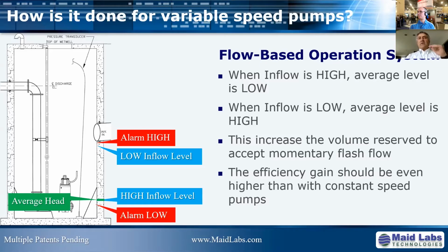So if the level continues to increase, you continue to increase the speed of your pumps. At some point, if it's not enough, it will get higher. But the way they are programmed right now, their goal is to run the pumps low in the well in order to accumulate capacity above it in case the flow rate increases. But when the flow rate is low, and historically it has been low at that time of day, then there's no reason to run your pump low. This is a way to be inefficient, it's like running your car with the brakes on. There's no reason.